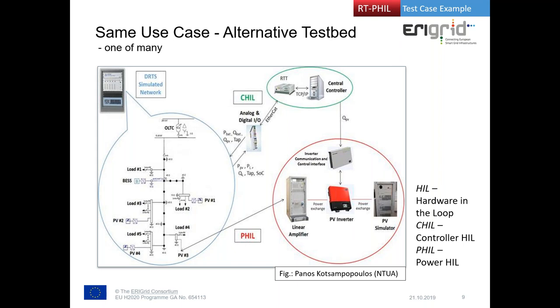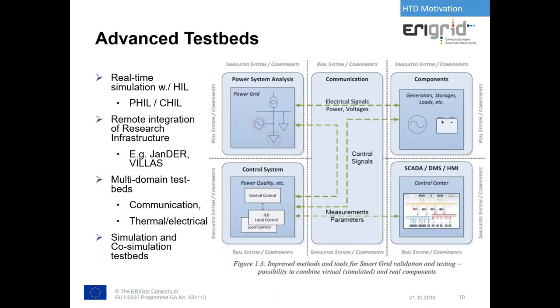A completely different setup is also imaginable — one suggested by our partners uses a digital real-time simulation of the distribution network, including PV inverters and battery storages, with a PV inverter in a power hardware-in-the-loop setup and the controller in a controller hardware-in-the-loop setup. These are two completely different physical realizations of a validation concept for the same use case, raising the challenge: how are they the same when physically so different? Beyond real-time simulation, we also work with remote integration of research infrastructure, multi-domain test beds combining communication, thermal, and electrical couplings, and co-simulation for larger-scale scenarios.